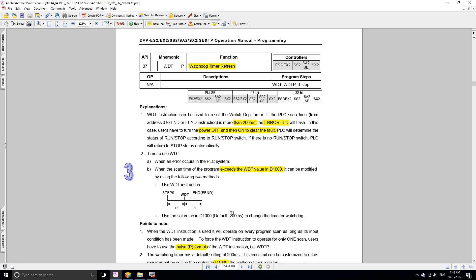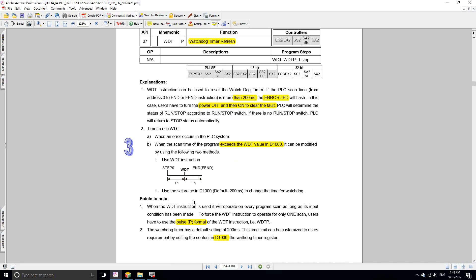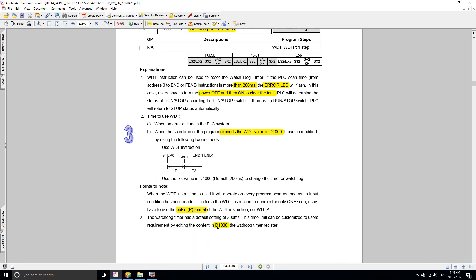If you know that your scan cycle is going to be, let's say 400 milliseconds, you can use the watchdog timer refresh or you can increase the threshold for the watchdog timer. Instead of the default 200 milliseconds, let's make it like 500 milliseconds.